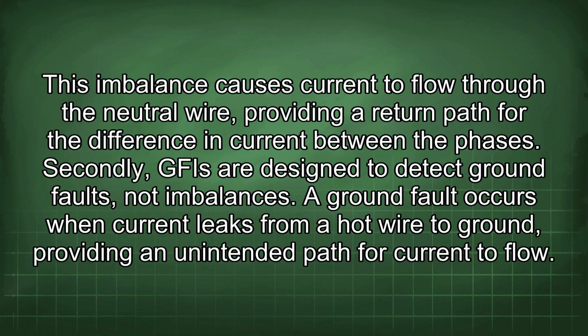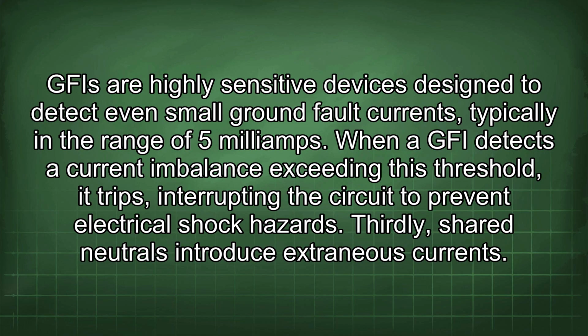A ground fault occurs when current leaks from a hot wire to ground, providing an unintended path for current to flow. GFIs are highly sensitive devices designed to detect even small ground fault currents, typically in the range of 5 milliamps. When a GFI detects a current imbalance exceeding this threshold, it trips, interrupting the circuit to prevent electrical shock hazards. Thirdly, shared neutrals introduce extraneous currents.